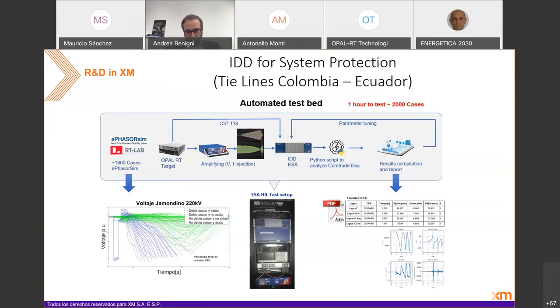After that, we capture all the results, the pictures of the events that were captured by this special protection scheme. We analyze those outputs, and through another Python script, we check if they fulfill the criteria of coordination with the protections in the south of the country. If they are coordinating, we raise a flag that the case passed, and we're able to detect if the logics built within this protection scheme coordinated or not with certain cases. We were able to run 2,000 cases in less than one hour, analyze all those results, and produce a report that says if the protection scheme or protection logic is coordinated or not with the protections upward in the interconnection.